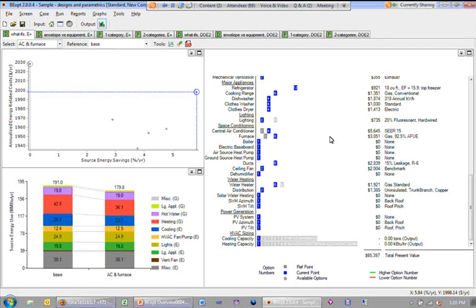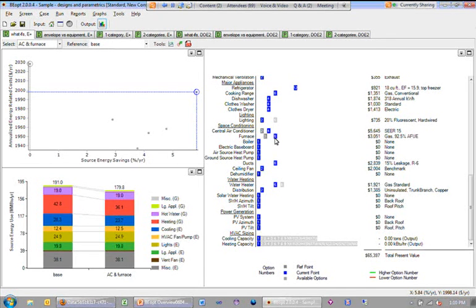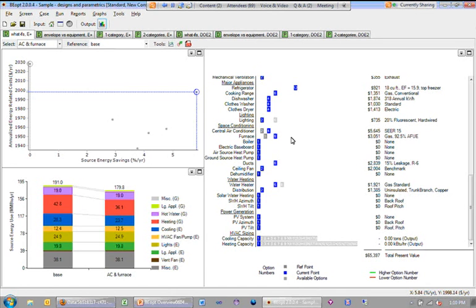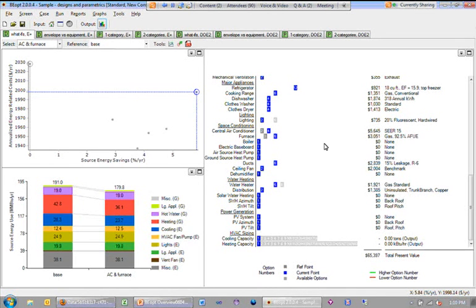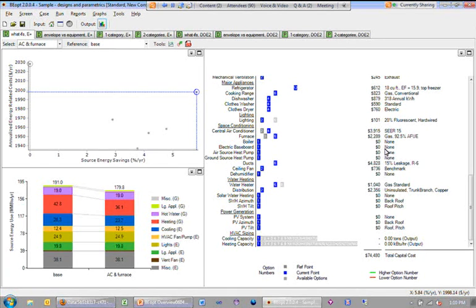Actually, because that replacement is going to go beyond year 30, if it was a 20-year lifetime, such that you replace something year 20, and then it would last until year 40, but we only have a 30-year analysis, there's actually a little bit of an adjustment or residual value that is calculated in year 30, the fact that you still have some remaining life on that equipment. So BEopt is taking that into account as well. But you could come here and you could look at strictly what is the capital cost, the upfront cost, year one, to put in this technology.